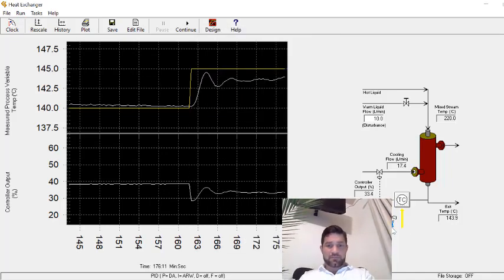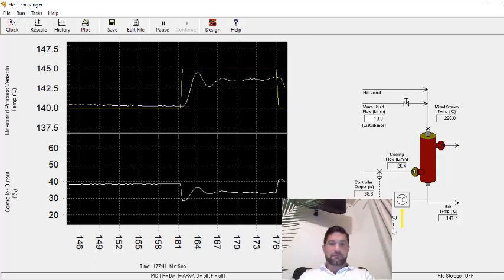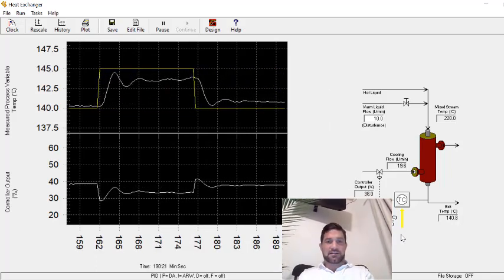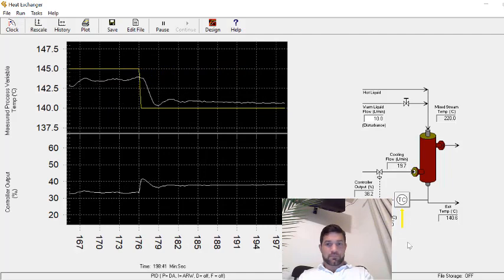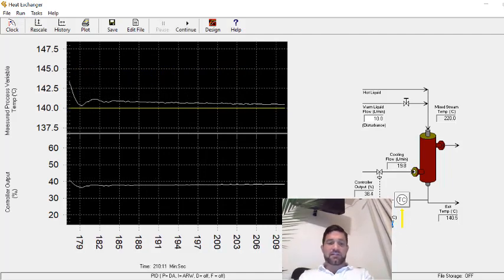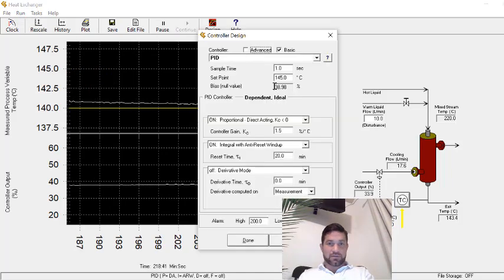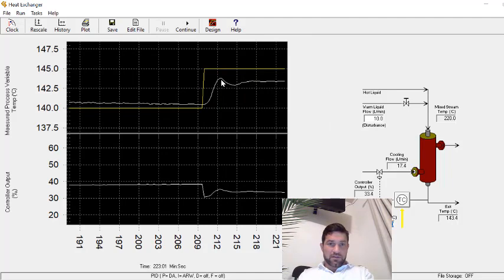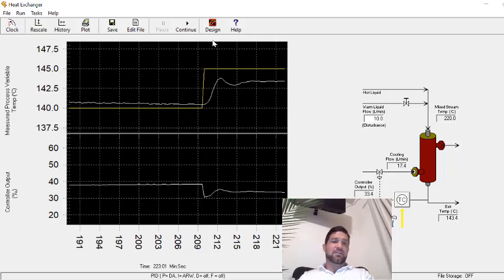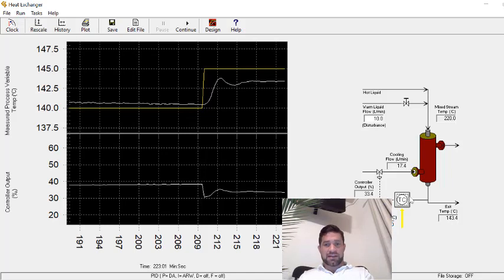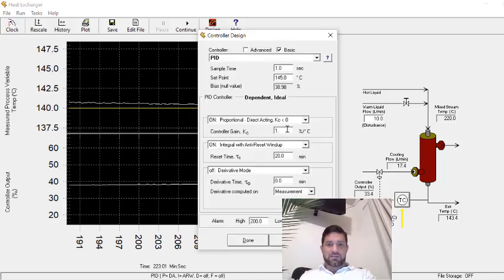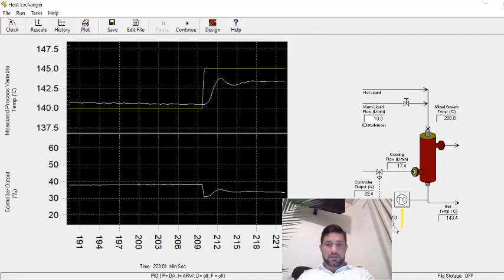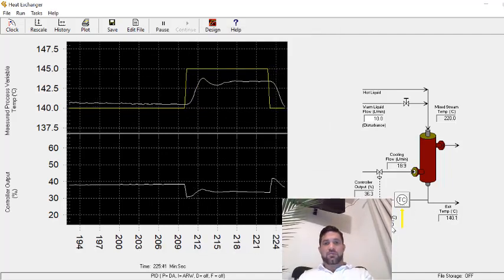Let's bring this down to 1.5. I want to step back down to 140. Should probably keep it the same and let the process settle out a little bit. On this change with the gain equal to 1.5, my first peak to valley looks to be a little bit less than my step change, a little bit less than 16%. Really what I want to do is print out this data and do a calculation, but I can kind of tell by eye it's a little bit low, so I'm going to change this to 1.8.